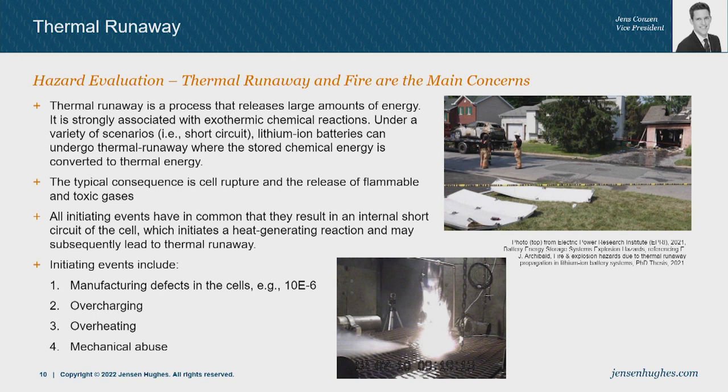A thermal runaway is an exothermic chemical reaction, if we remember that from our high school and university days, unless you're a chemist and deal with it every day. It's a very accelerating reaction in which the typical consequence is that the cell will rupture, burst open, and release fairly large amounts of flammable gas. In some cases, depending on the chemistry and the state of charge, that release of gas might catch fire. So we can have burning reactions or venting reactions with the thermal runaway.